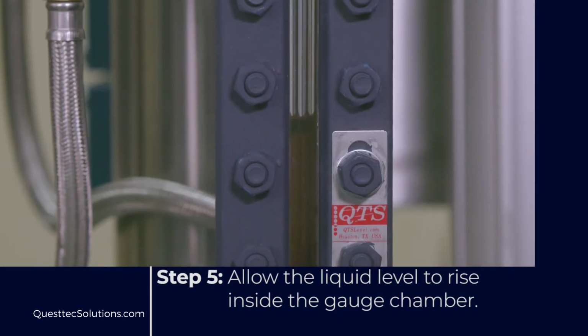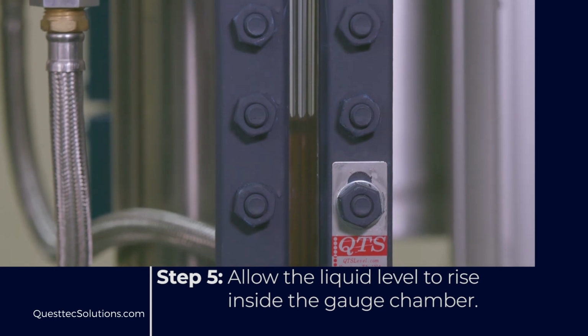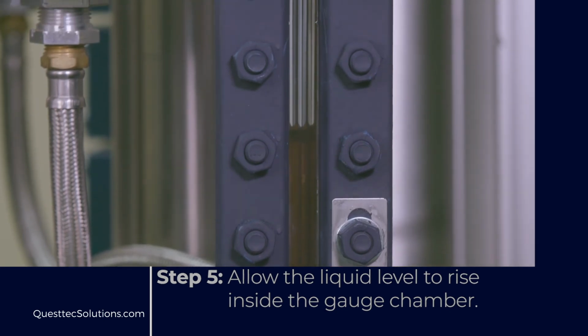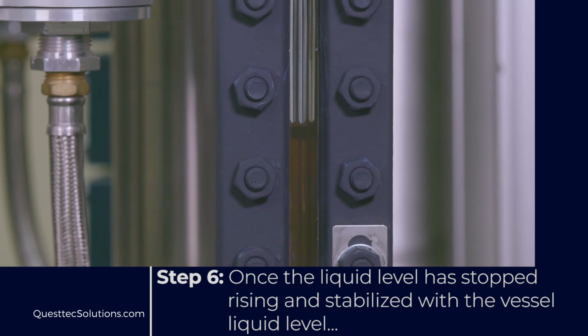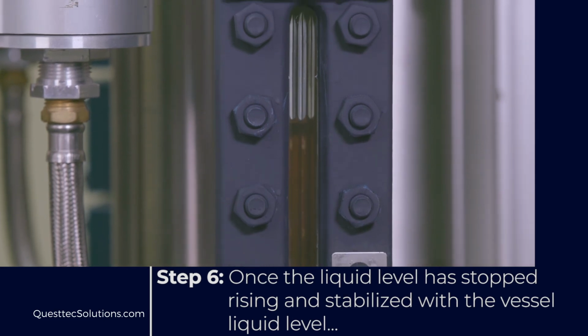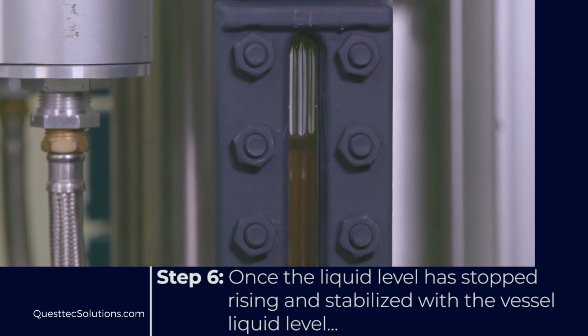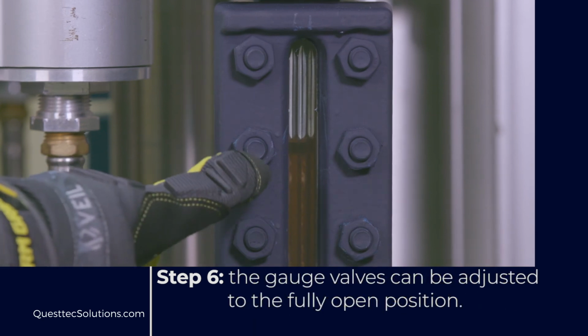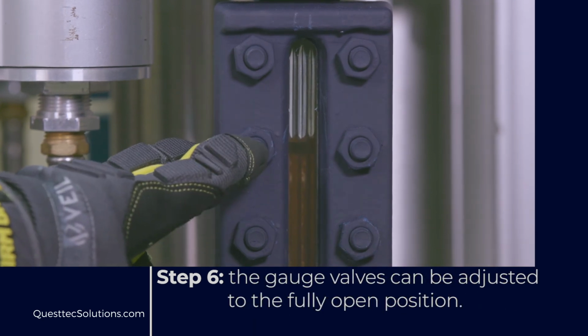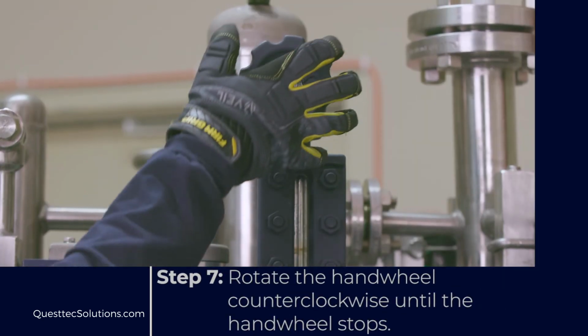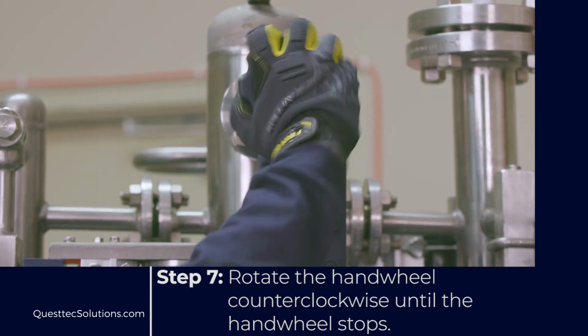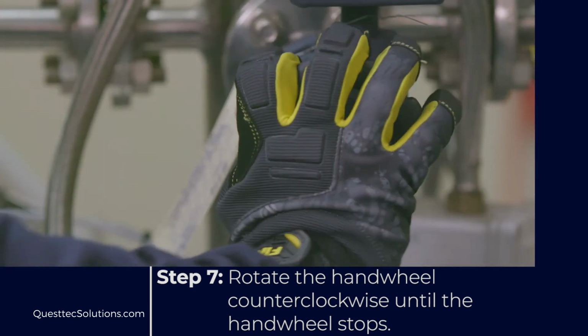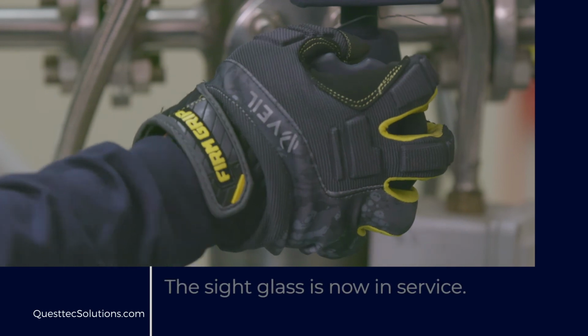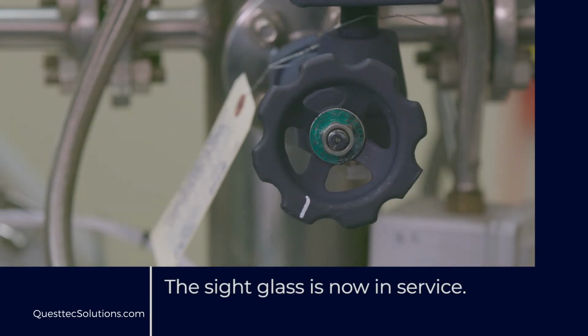Step 5. Allow the liquid level to rise inside the gauge chamber. Step 6. Once the liquid level has stopped rising and stabilized with the vessel liquid level, the gauge valves can be adjusted to the fully open position. Step 7. Rotate the handwheel counterclockwise until the handwheel stops. The sight glass is now in service.